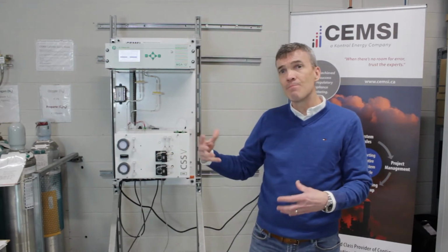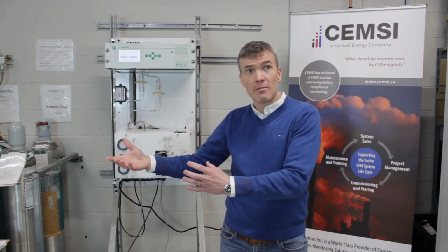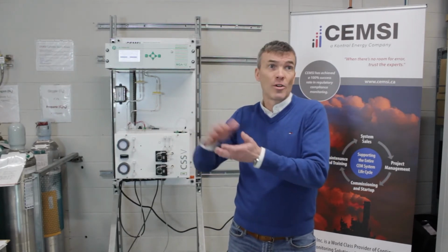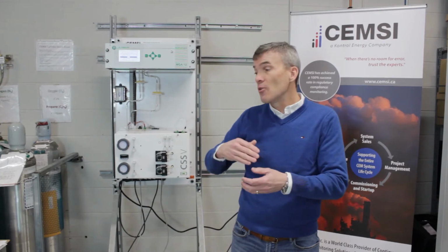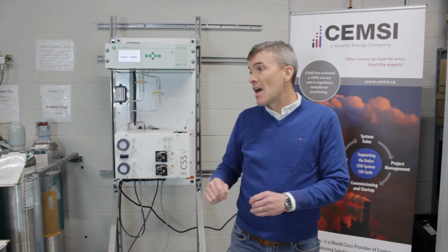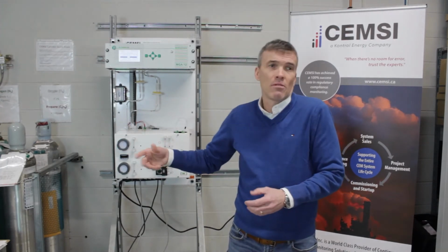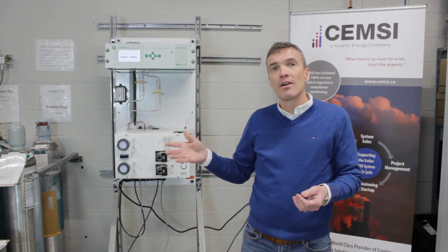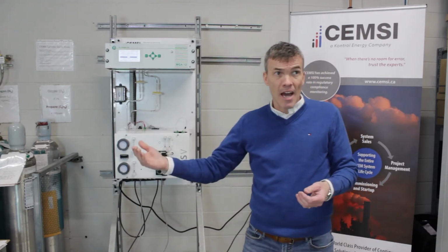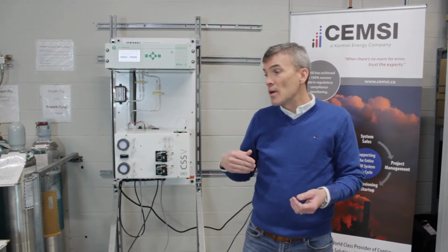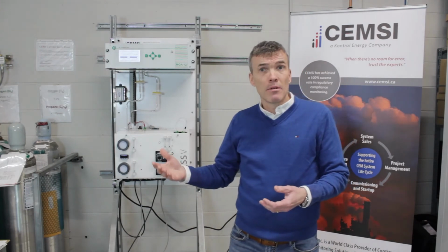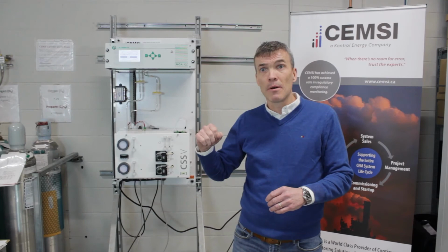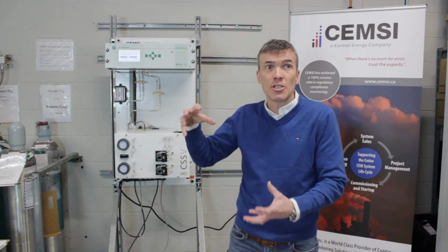So in every application, temperature makes a big difference, whether you actually cause a chemical salt to form or dissolve, something to knock out or to pass through as a gas. And then we talk about agitation, the movement. Well, I mean, it's a sample gas. Who's mixing? No one does, but realize what we have. We have pressure from the stack, which is a force. We have your pump, for those that use piston-style pumps. You have a negative and positive stroke of a piston-style pump. That creates pressure, expansion, contraction.